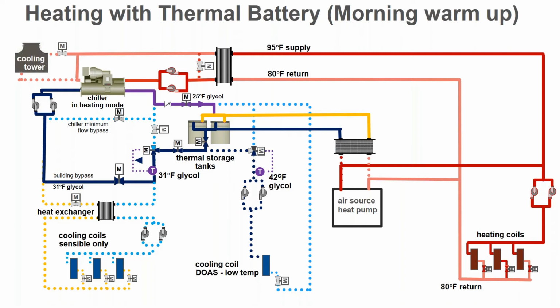And it actually turns out to be very similar to what you do in air conditioning with what we'll call the ice storage tank. So remember when I spoke about a partial storage system where you have a 1,000-ton chiller and storage, and the storage makes enough cooling at night. The chiller makes enough cooling at night to then run this smaller, half-size 1,000-ton chiller, and the storage helps that 1,000-ton chiller meet the 2,000-ton design load. So you've actually designed the chiller plant so all it has to do is meet the average cooling load on design day, the 24-hour average. And most buildings don't have much cooling load at night, and that's why we can do that.